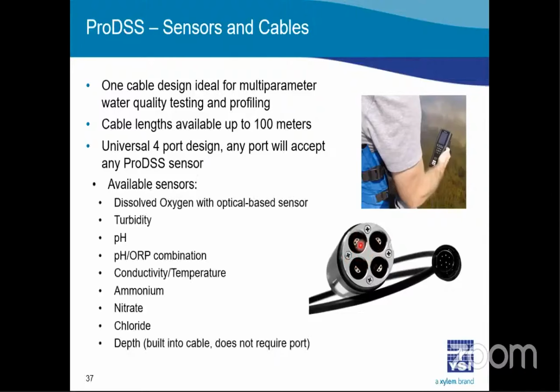These are the available sensors for the Pro DSS: dissolved oxygen based on the optical sensor method, turbidity, pH or pH ORP, conductivity and temperature, ammonium, nitrate, chloride, and also depth. That is good for well monitoring measurement systems, or for profiling on a river or lake.